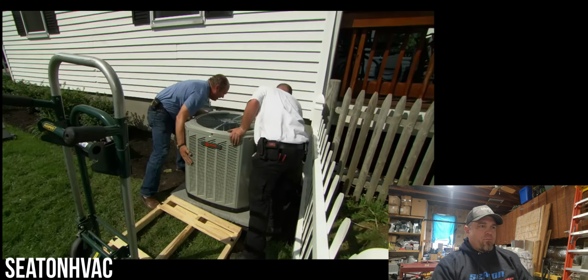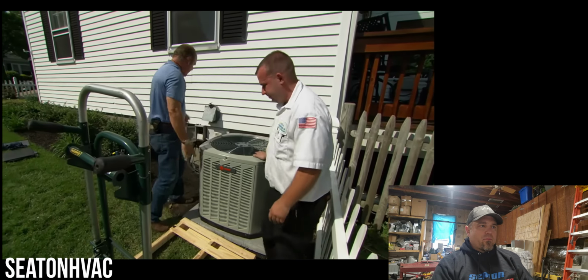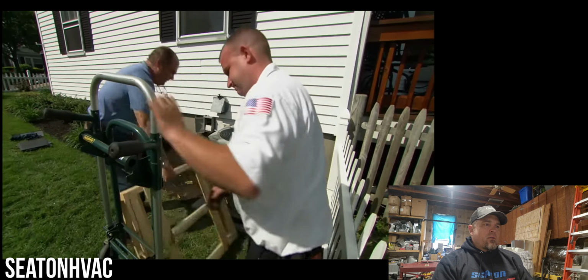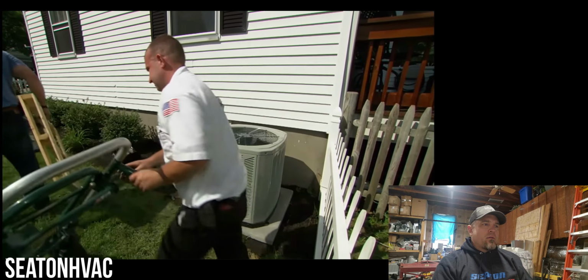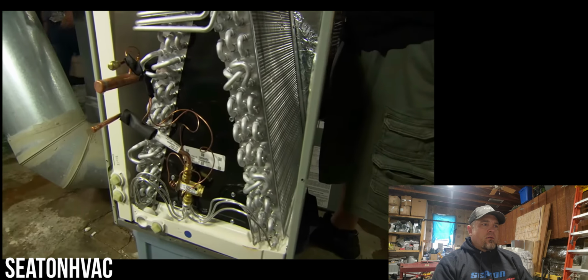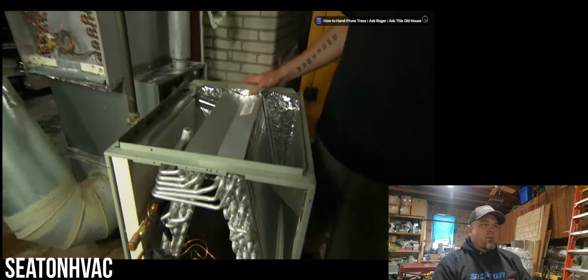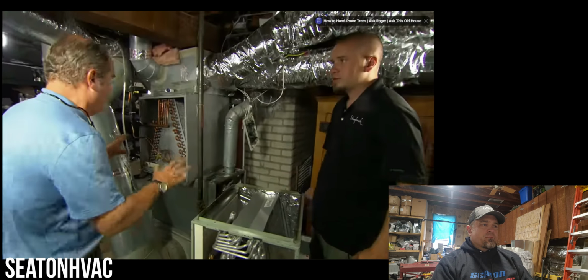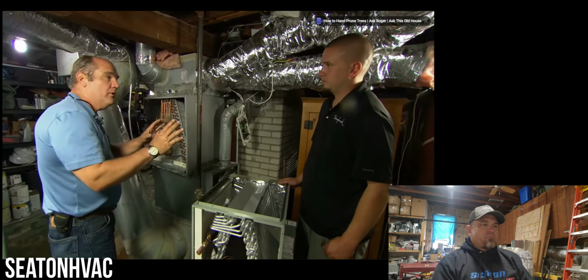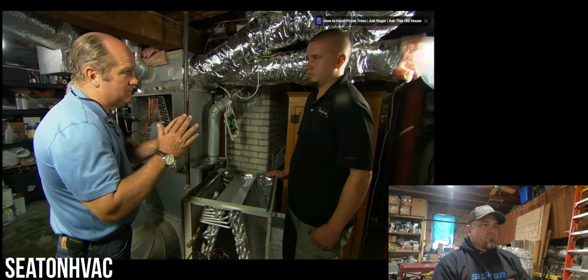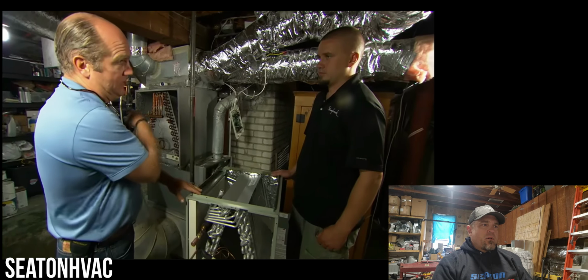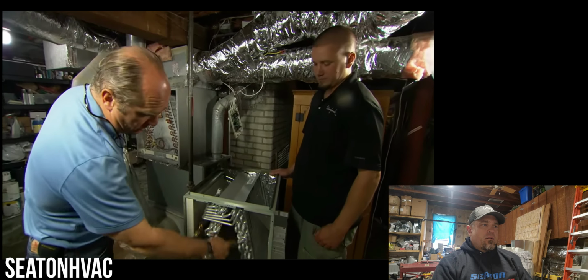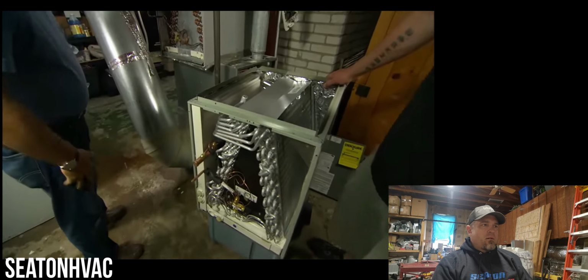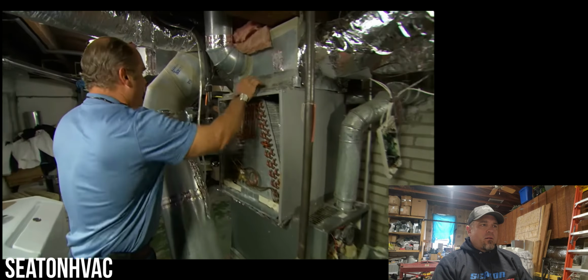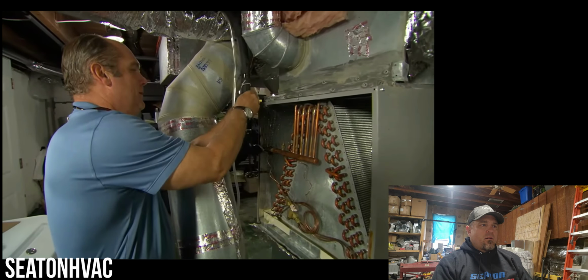All right, with that in place, now we just have to remake our connections. All right, we got the connections made on your new condenser outside. Now we have to think about inside. We got to get rid of this old coil and put a new one in. And the important thing is that this has to be the same size tonnage as the outdoor. 3-ton, 3-ton. So this is your new evaporator coil right here. And it's going to start by getting the old lines cut away so we can get rid of the old coil.